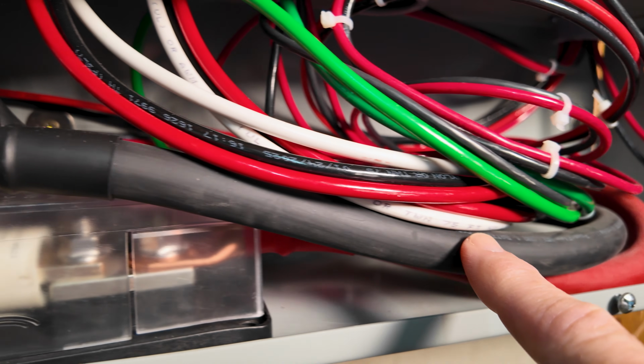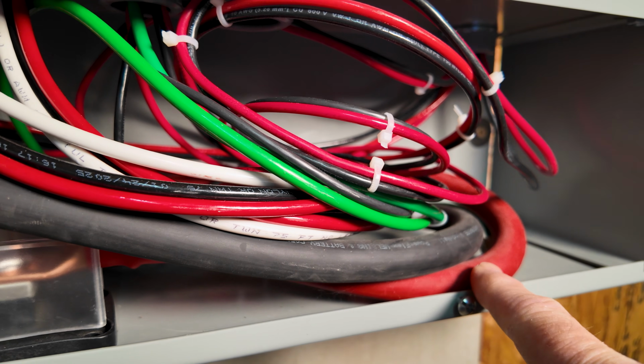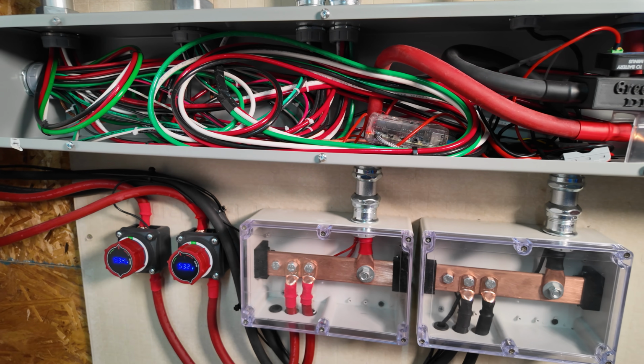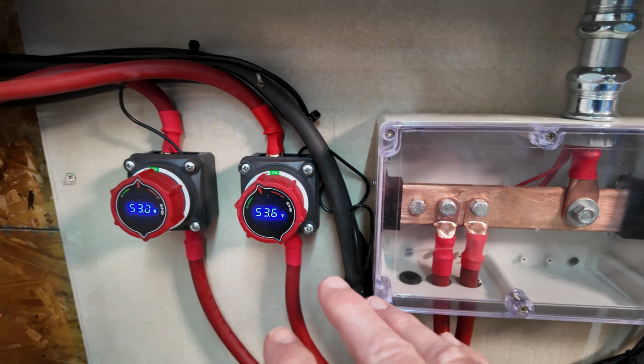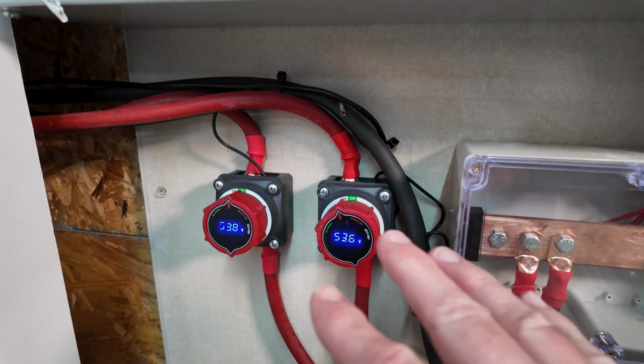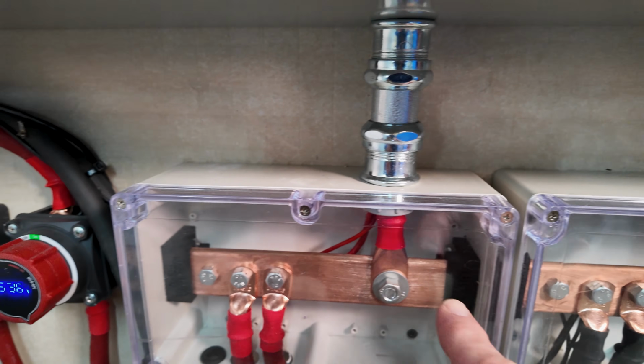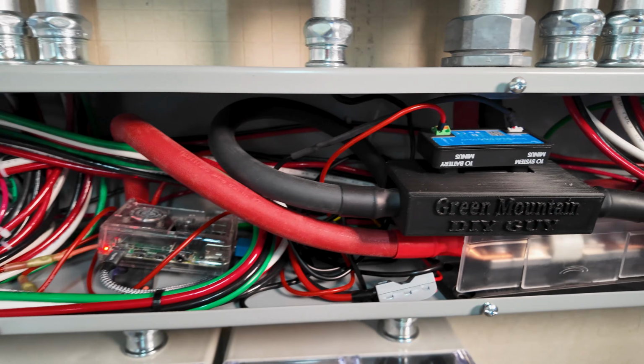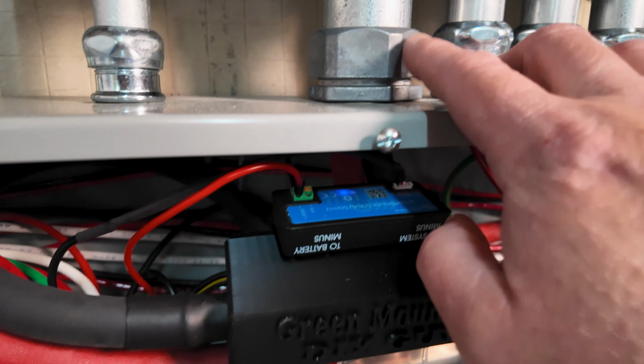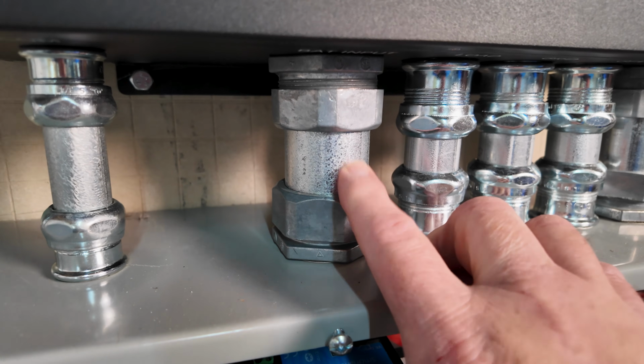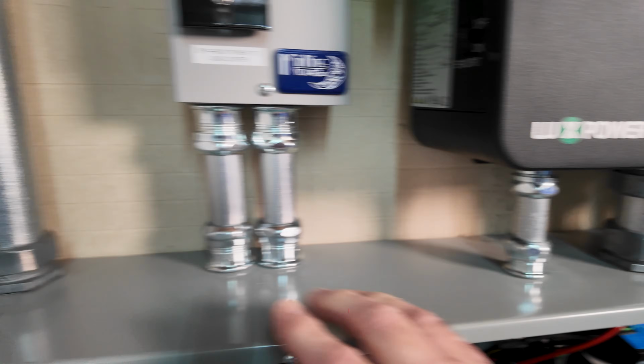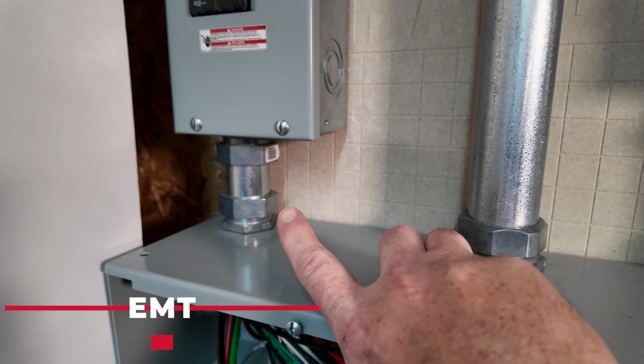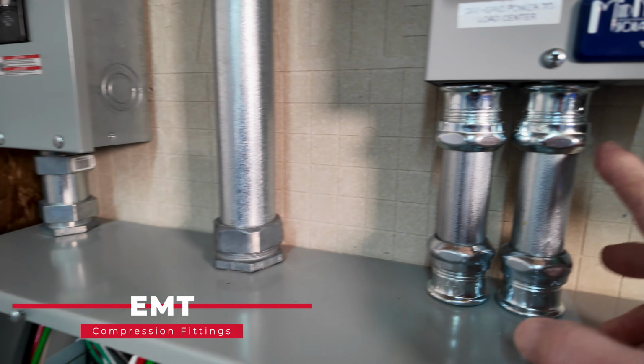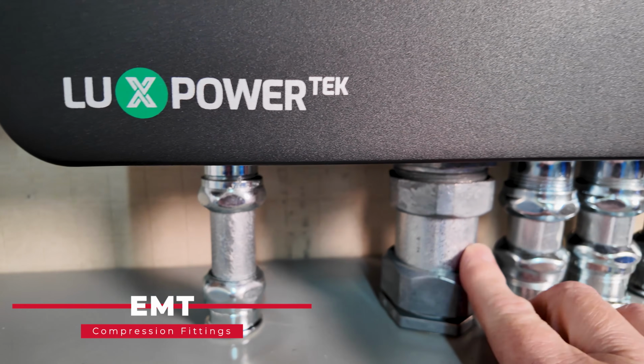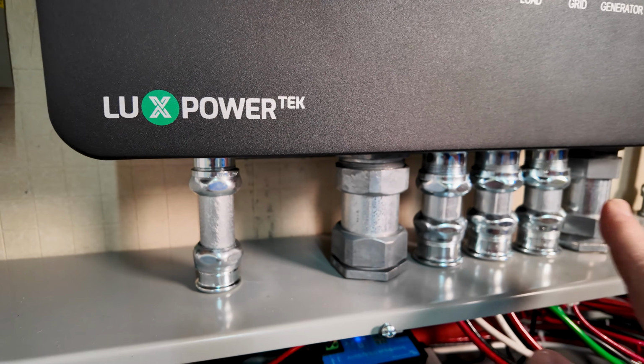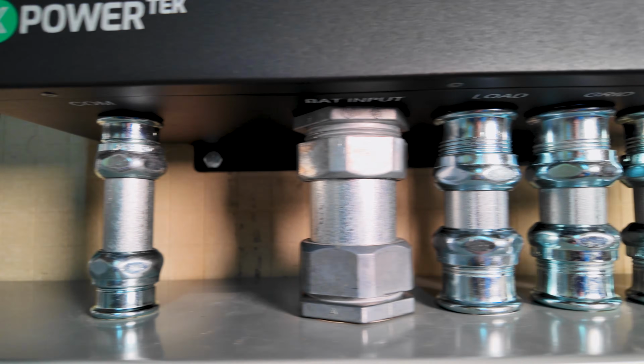And then all my DC wires here, I'm using 4-aught, that's coming from the bus bars here. Everything else going to the batteries is 2-aught, and then it combines, and then 4-aught going up, and that eventually works its way up through this 1.25 inch steel pipe. All my fittings here, EMT conduit, either stainless steel or just regular steel, depending on what they had at Lowe's and so forth. Again, real professional look there.